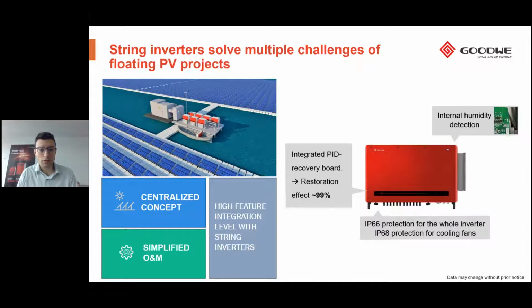Floating PV comes with a lot of humidity, with a lot of exposure to water, splash, and so on. And we can support this with a set of different features. You see here an integrated PID recovery board, for potential induced degradation, which is a phenomenon which can happen in certain modules. That's a recovery board that puts a reverse voltage on the panels, which we are integrating into the inverter, and that helps the panels to recover from such a PID effect. Also, the inverters have an IP66 protection rating for the whole inverter and IP68 protection for the cooling fans. So IP rating is critical. Inverters will be exposed to water splash, will be exposed to water in this environment. So the IP66 rating makes sure that the inverters under strong water jets are fully tight and fully waterproof.